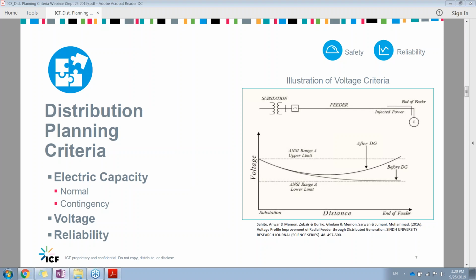So underneath that schematic of the system is a simplified graph showing voltage criteria that a planner might look at. It shows the standard range of voltages that are acceptable. It's called out as ANSI range A. That's the industry standard that's applied. And so there's two lines there, one showing before DG or DER is installed. And what you see there is a typical declining voltage profile. Everything is within limits that was studied by a planner to assure the voltage range was met.